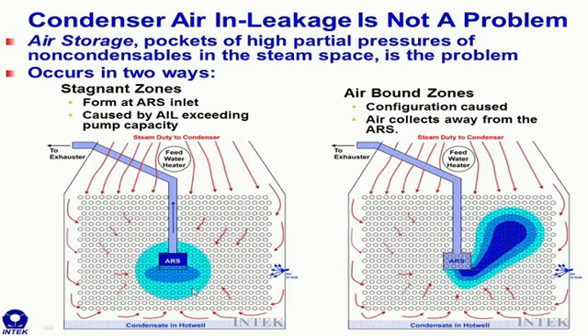The second way air is stored is in air-bound zones. And these are configuration caused. And what I mean by that is that the tube bundle arrangement, the baffles inside the tube bundle, and the air removal section configuration is of a poor design and allows these pockets to persist and collect in areas away from the air removal section. And so the only way to vent them is for these air-bound zones to grow to a size such that the air that's feeding them can be exhausted from a corner of the air removal section.